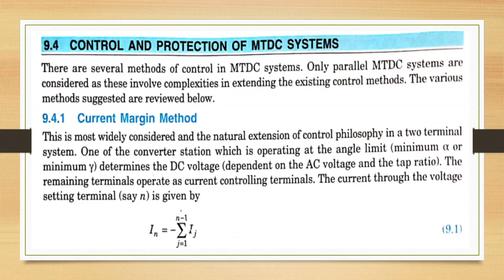The current controlling terminals operate with a voltage margin which may become 0 or negative during disturbances in the AC system. As even small disturbances can affect the voltage margin, it is necessary to maintain the current and power distribution in the system with minor changes during the disturbances. And this is possible if current control is provided at the voltage setting terminal such that it tries to maintain the same current as before.